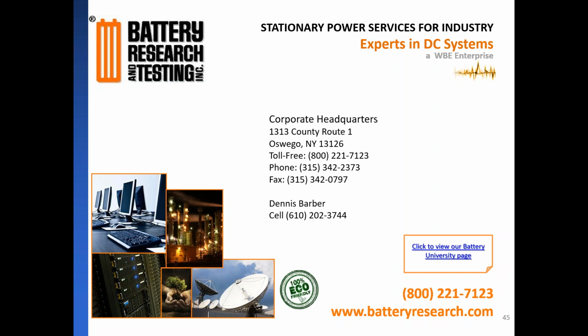So we would go with two switch mode rectifiers. They're so much cheaper. They're so much smaller. And now you have the redundancy, so you can take one out of service for maintenance, or if it just needs to be replaced, and not have to worry about a temporary battery. Likewise, footprint gets to be an issue and stuff like that.